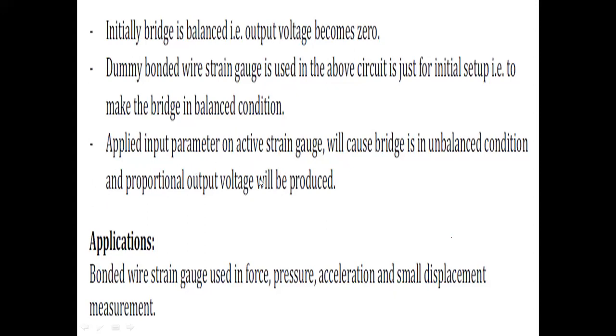We apply stress, strain, or weight causing displacement to the strain gauge, which causes the bridge to go into unbalanced condition. The resistance of that particular branch changes, and the bridge becomes unbalanced. Then the unbalanced bridge gives an output voltage proportional to the input.